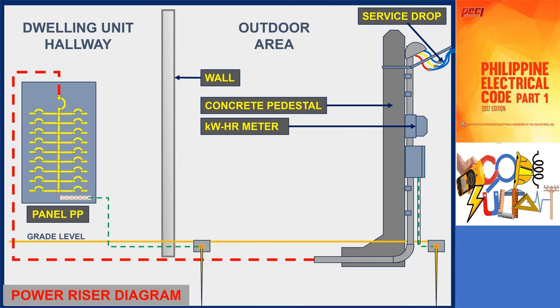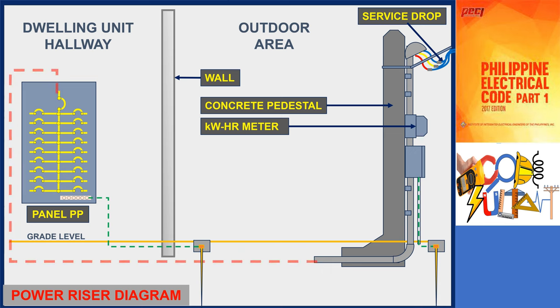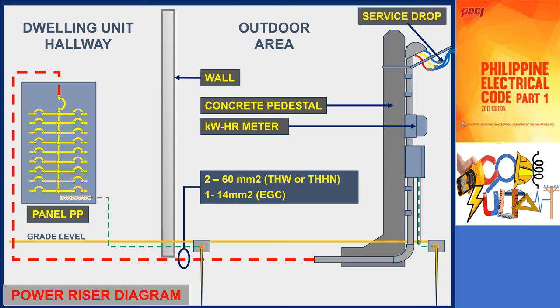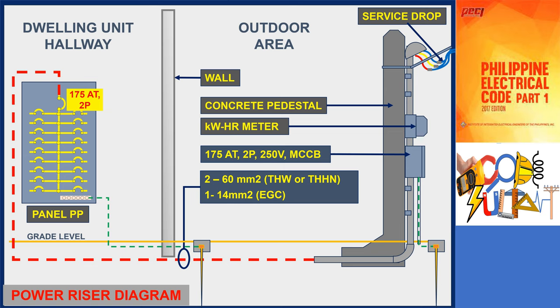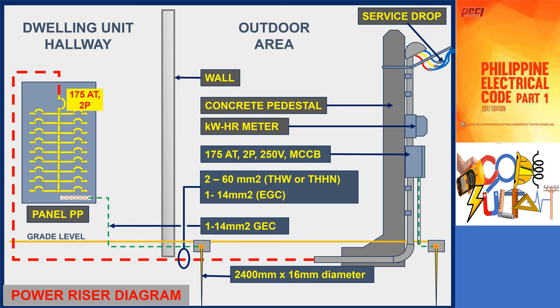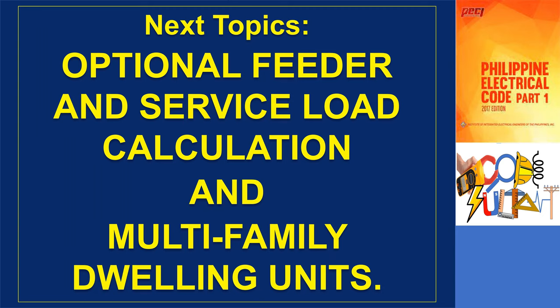Going back to the power riser diagram, the feeder and service entrance conductors consist of two 60 square millimeter THW or THHN conductors along with a 14 square millimeter conductor. For feeder protection, a 175-ampere trip, 2-pole, 250-volt rated molded case circuit breaker will be used. The same type of circuit breaker will be employed for the service equipment. The grounding electrode shall have a minimum length of 2.4 meters and a minimum diameter of 16 millimeters. Thank you for tuning in. In our next topics, we will discuss optional feeder and service load calculation and electrical system design for multifamily dwelling units.